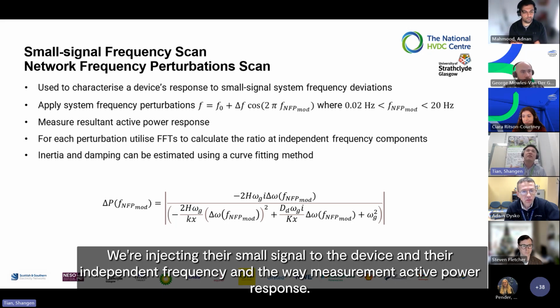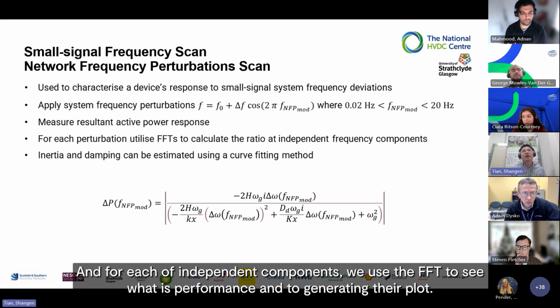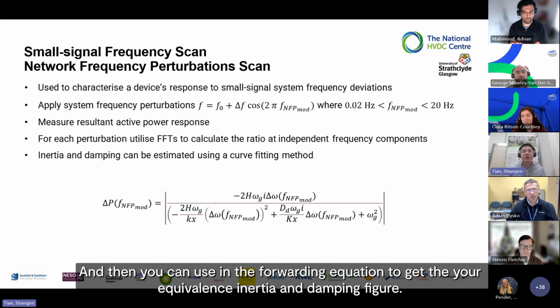We inject a small signal into the device at an independent frequency and measure the active power response. For each independent frequency component, we use FFT to see the performance and generate the plot. You can use the following equation to get the equivalent inertia and damping factor.